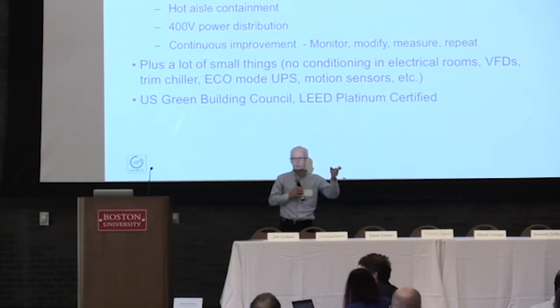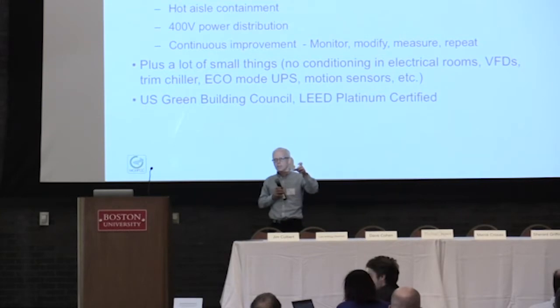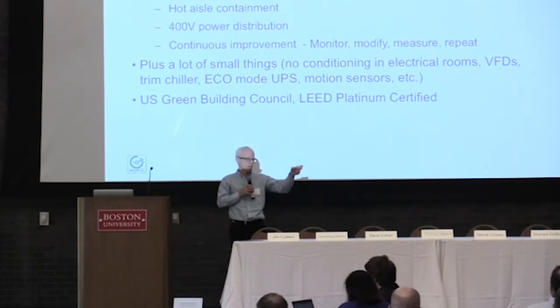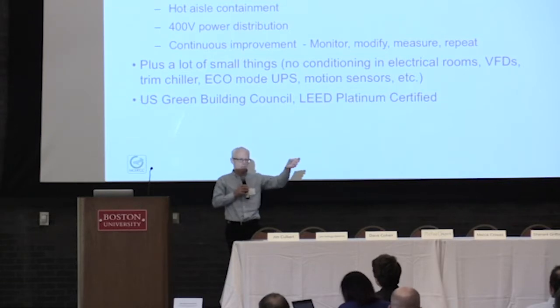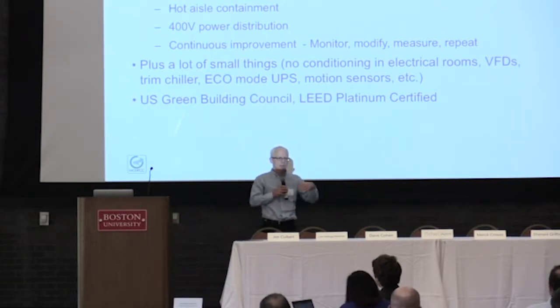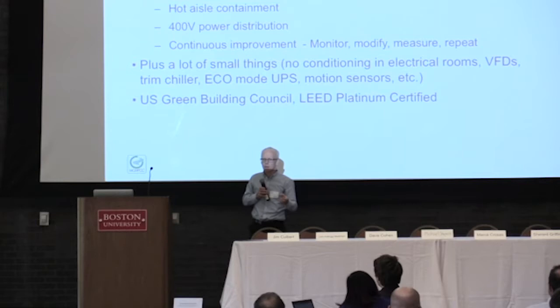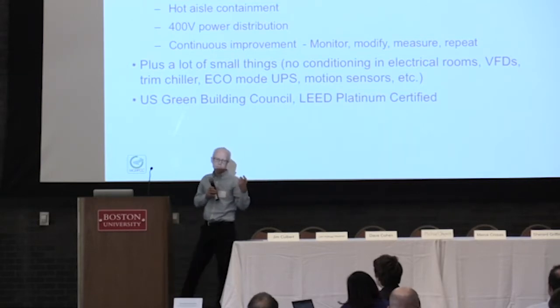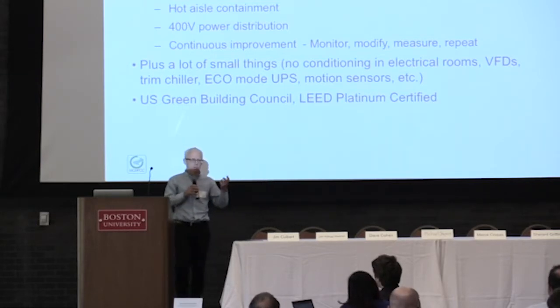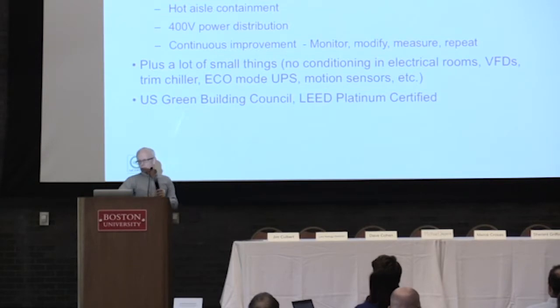We use in-row cooling along with hot aisle containment, a very efficient way to cool computers. Essentially, every 2 computer racks pair with an air conditioner, and with hot aisle containment those heat exchangers become very efficient. We keep the delta T across them very high.